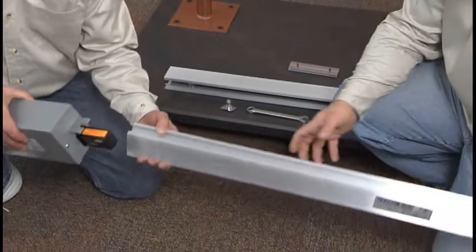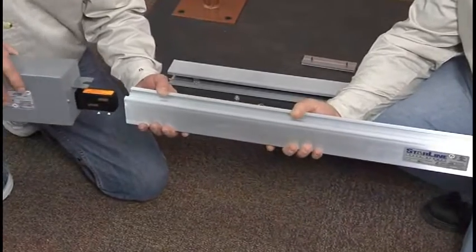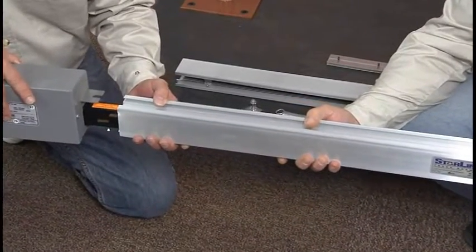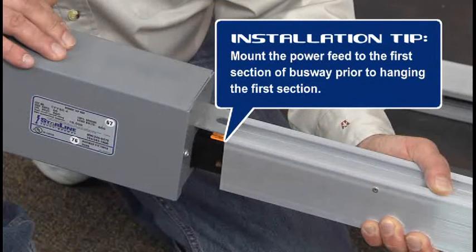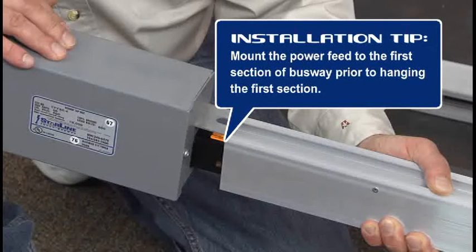Begin installation at one end of the busway, preferably at the end where the power source is located. A helpful hint is to mount the power feed to the first section of busway prior to hanging the first section. Then begin with that assembled section of busway.